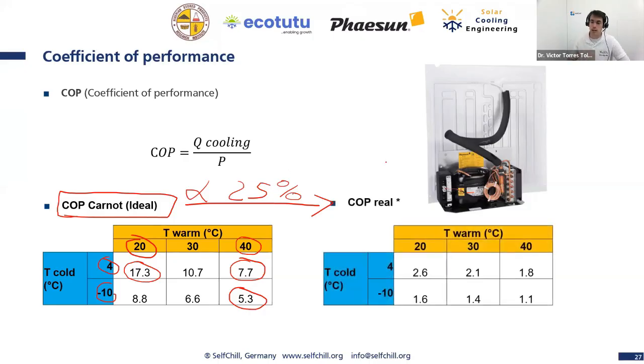I'm going to show you real measurements. We measure the energy consumption, and we measure the cooling energy that was delivered by the evaporator plate. At 20 degrees ambient temperature and 4 degrees cooling temperature, we get 2.6, 260%. At 40 degrees ambient temperature, we are still at 1.8. I invest 1 kilowatt hour of electricity, I get 1.8, 180%. Even if we are producing ice at minus 10 degrees and the ambient temperature is 40 degrees, we are still working above 1, 110%. I invest 1 kilowatt hour of electricity and get 1.1 kilowatt hours of thermal energy, cooling energy. So our cooling unit almost always works with a COP above 1. I hope I was able to convince you; these were real measurements.